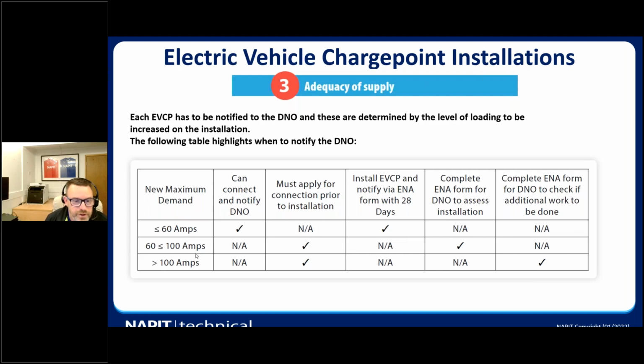If it's between 60 and 100 amps, it must be applied for connection before installation. So you complete the form and issue it to the DNO. If it's over 100 amps, you must apply for connection, the form must be completed, and the DNO will check to see if any additional work is needed, such as upgrading the supply for that installation. So when we look at installing EV charge points, you've got to look at the requirements for notification to the DNO.